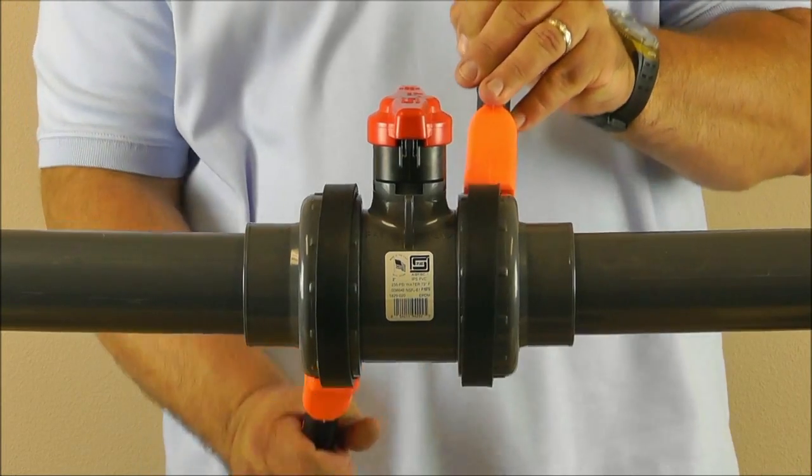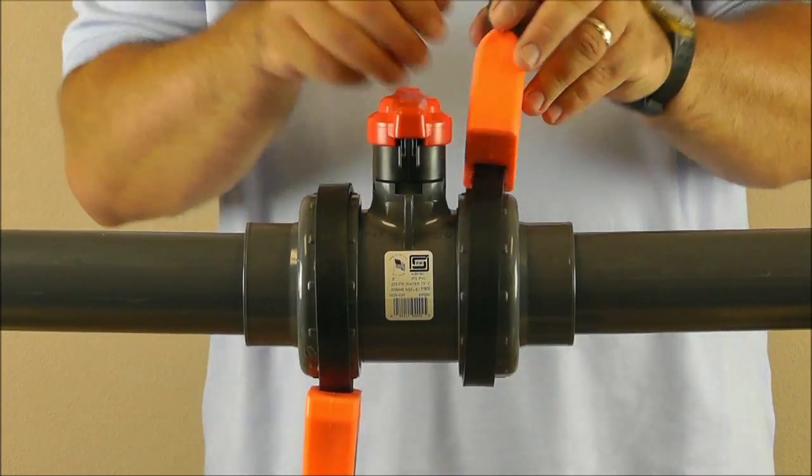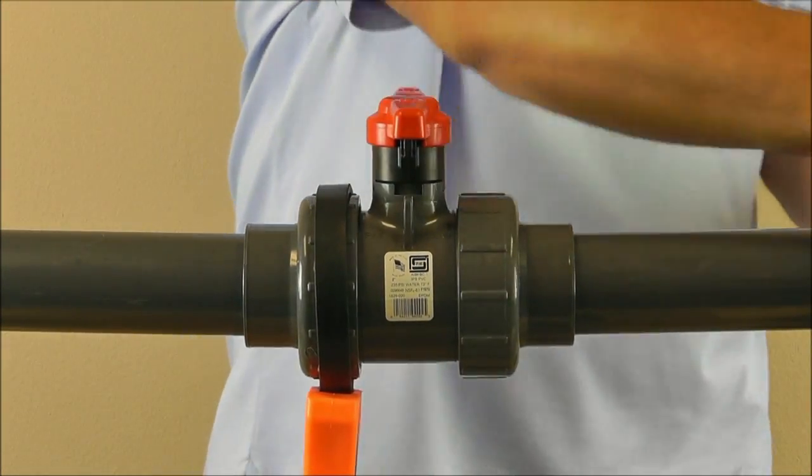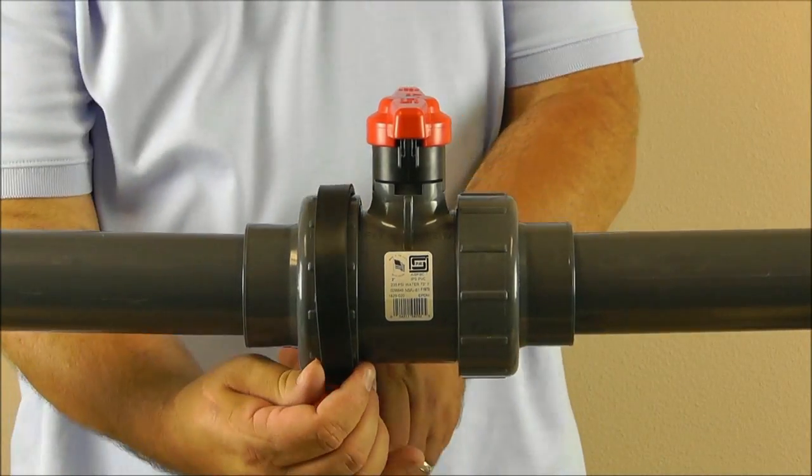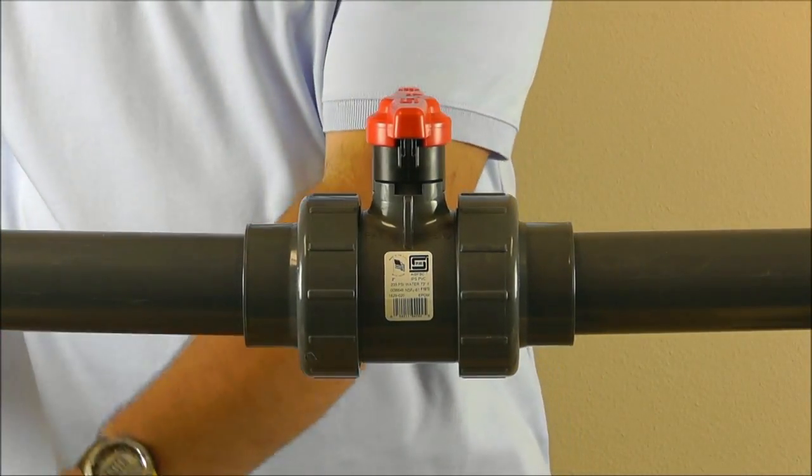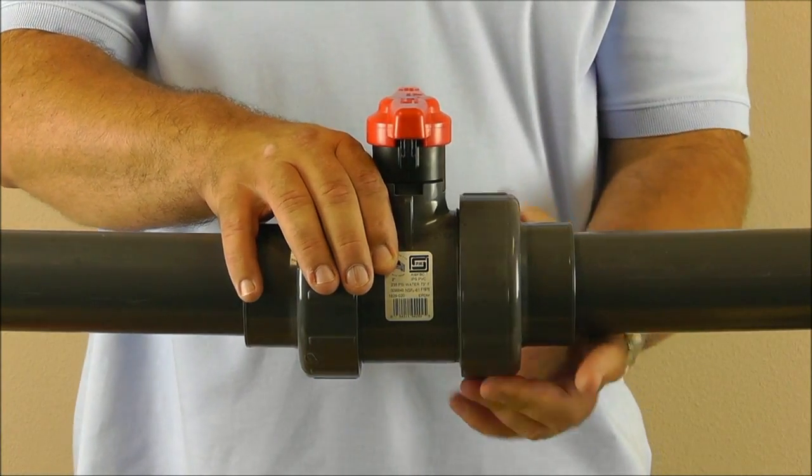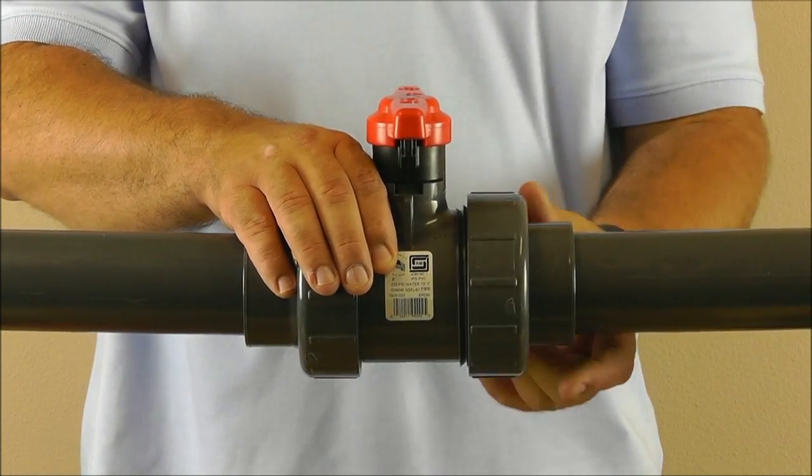Your installation begins by shutting down and draining the system or line the valve is installed within. Back off union nuts by hand or with strap wrenches and remove valve cartridge. Place the cartridge on a clean solid surface to work on.